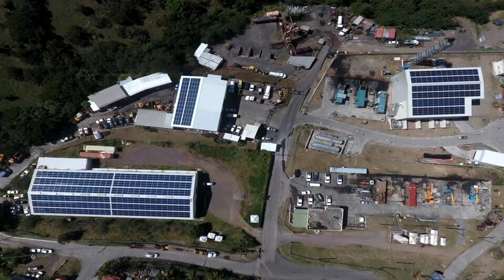And up here are our 6 inverters. The system was designed to produce a peak of 288 kilowatts DC, and each of these inverters can do 50 kilowatts, so we've got a total of 300. That's important, because a lot of times when people design the system, they go cheap on the inverters, so the solar can actually generate more electricity than the inverters can deal with.